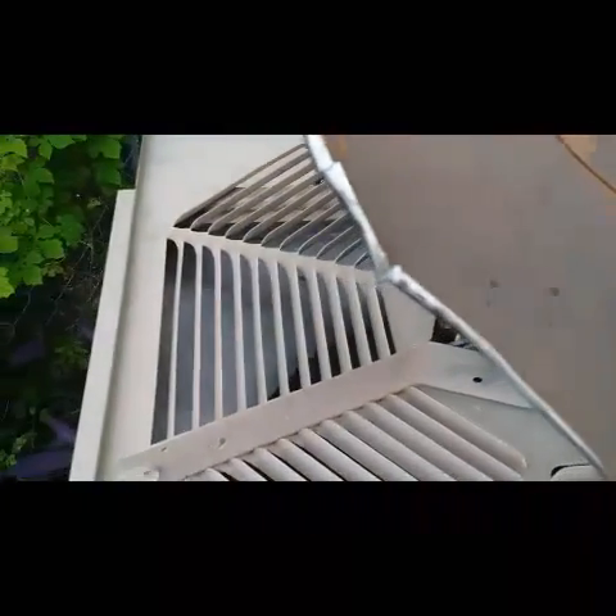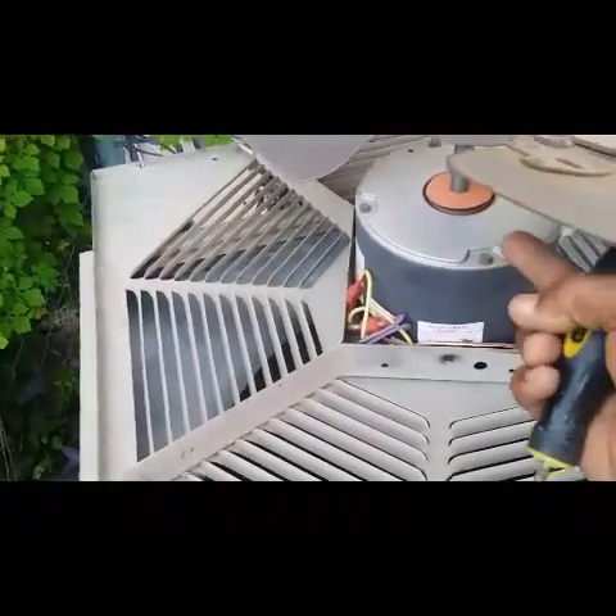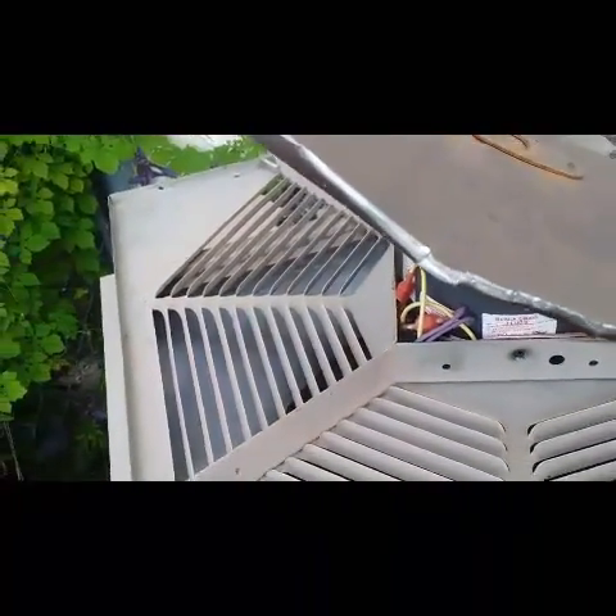One of the screws fell out, so it was hanging over on one side. Now look — all my blades are bent. I have to straighten out the blades. For right now I'm just going to take pliers and straighten these out, then add a few more screws right here. When it came loose the blades started to hang and bang underneath inside this canister — you can see where it was banging right here. That's what destroyed these, but they're not destroyed all the way.